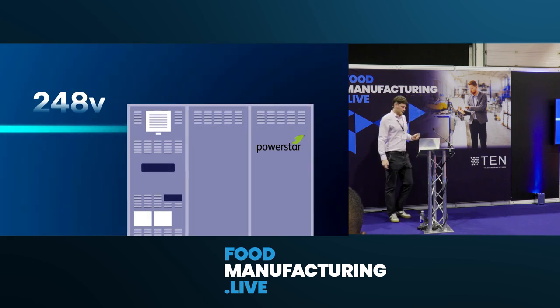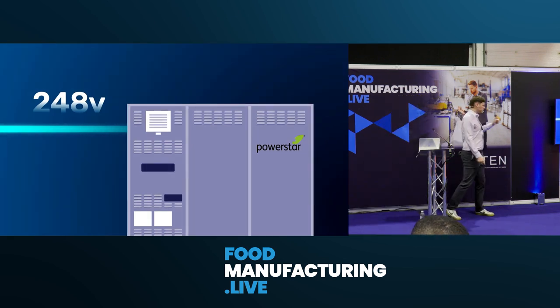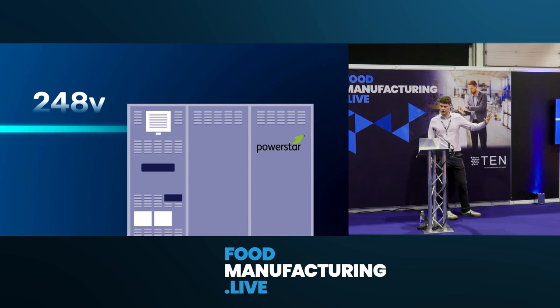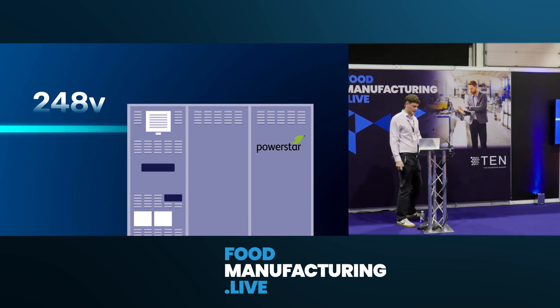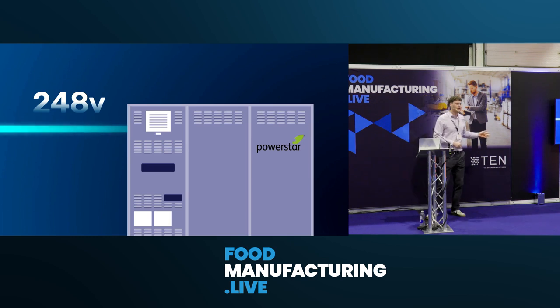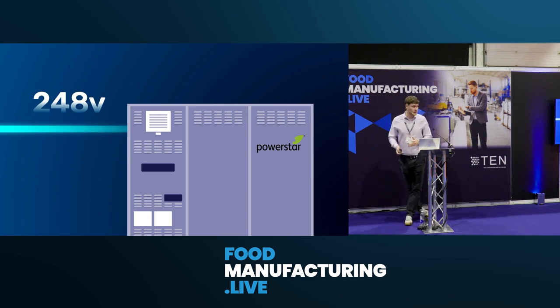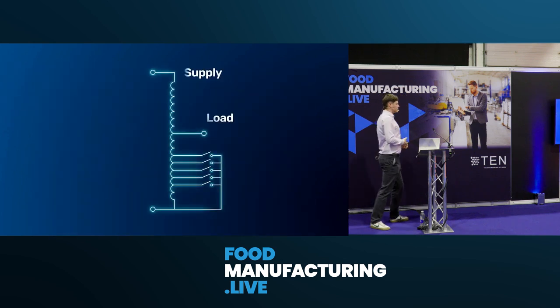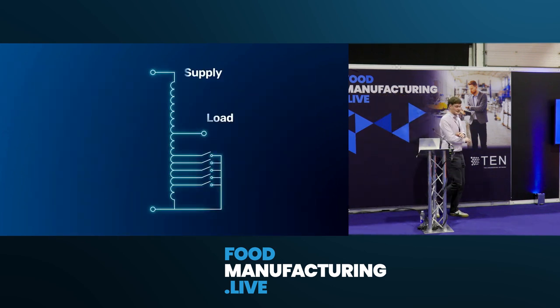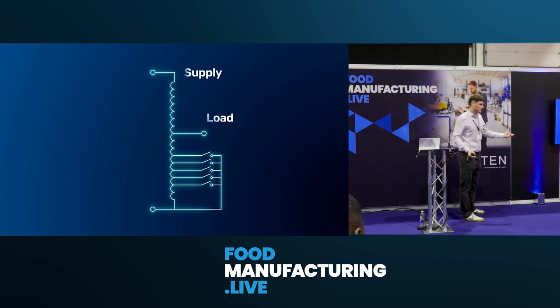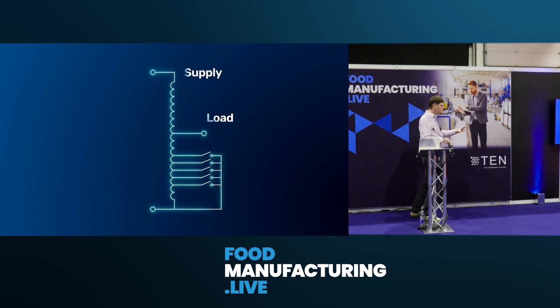So this is a VO unit. We supply the 248 into it, so we divert your incoming tails from your transformer or out of your switchgear into the voltage optimization device. Now, this device isn't a box of electronics. It is half, but not all of it. It's not as complicated as a lot of people make this device out to be. It's the control of it that gets hard. So, inside a VO device, and this is every VO device out there, this isn't just Powerstar, this is every VO device that's out there, is an auto transformer. So people think, oh, we can just tap transformers down, we achieve the same effect. Yes. Not to the resolution that we have here, not to the control that we have in our devices, but we have an active compensation device inside there.